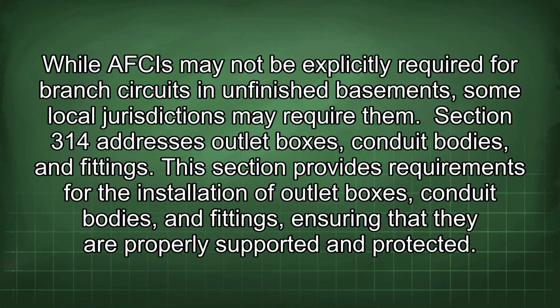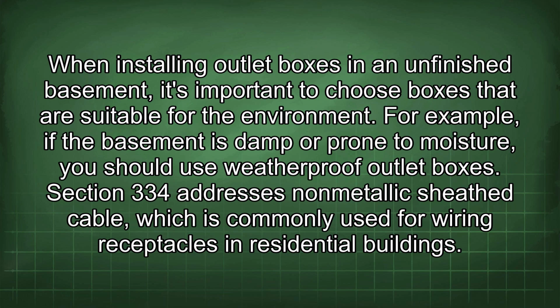Section 314 addresses outlet boxes, conduit bodies, and fittings. This section provides requirements for the installation of outlet boxes, conduit bodies, and fittings, ensuring that they are properly supported and protected. When installing outlet boxes in an unfinished basement, it's important to choose boxes that are suitable for the environment. For example, if the basement is damp or prone to moisture, you should use weatherproof outlet boxes.